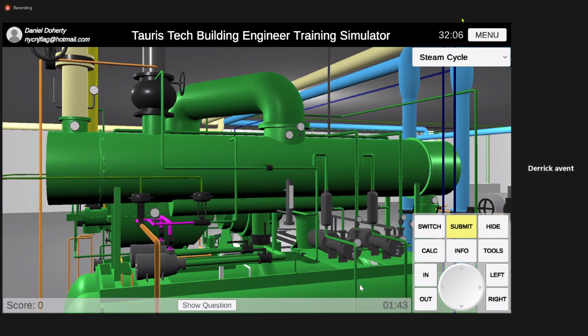Return condensate. So the job of those two valves is to keep the hot well full with condensate. You can't have that condensate start coming up into the surface condenser, right? Because now you can't condense because there's condensate in there. Correct. So those valves keep that level. It would have nowhere to go. Right. If you didn't throw it out, this whole thing would sort of fill up with water. And flood. Yeah, exactly. So it would have nowhere to go. That's why that overboard valve, if the level gets too high, then it starts dumping water out of the surface condenser so that it's at only the hot well level.